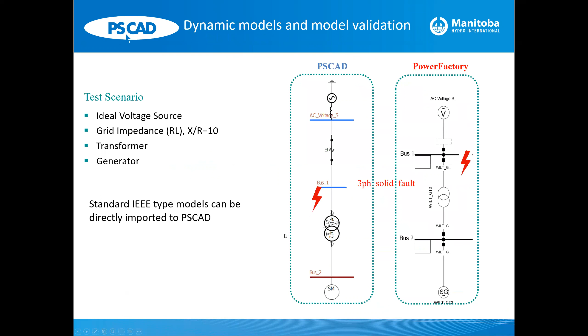So what we generally do is have the network first see a voltage source with the same conditions as the wind farm. This path is not seen by the network until T release, say at 5 seconds, when the system initializes with a source. Then at T equals 5 seconds, the source disconnects, and the wind farm with all its controls, fully energized and initialized, connects to the grid.